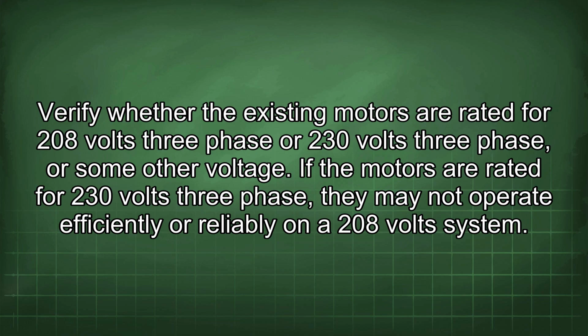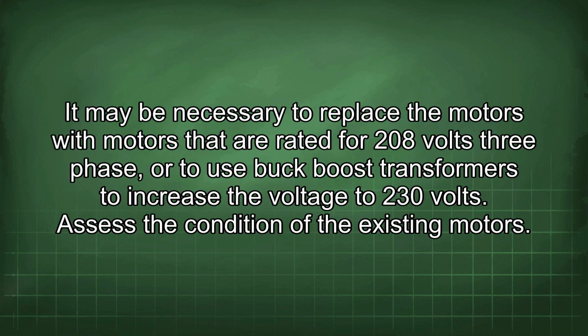If the motors are rated for 230 volts three-phase, they may not operate efficiently or reliably on a 208 volt system. It may be necessary to replace the motors with motors that are rated for 208 volts three-phase, or to use buck-boost transformers to increase the voltage to 230 volts.